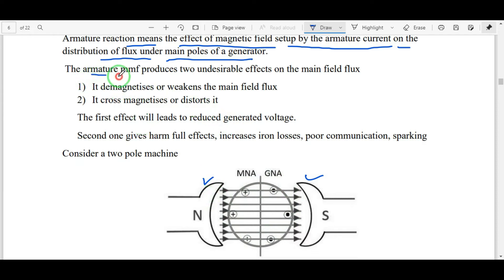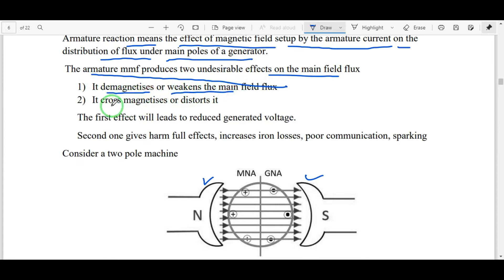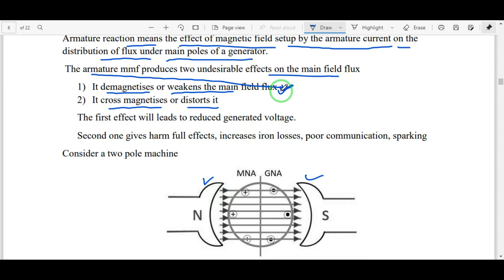Armature MMF produces two undesirable effects on the main field flux. The two effects are: first, de-magnetizing or weakening the main field flux; second, cross-magnetizing or distorting it. De-magnetizing effect means the armature flux is opposite to the main field flux, so both cancel and the main field flux is weakened. Cross-magnetizing effect means the main field flux direction changes because of the armature flux.